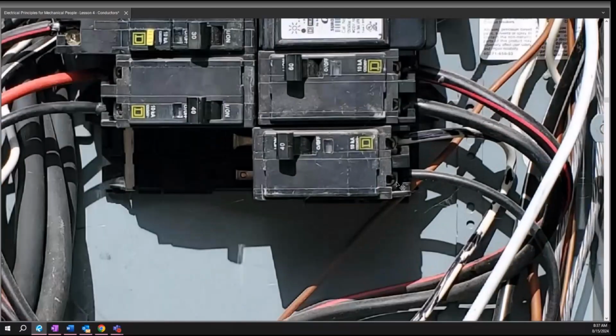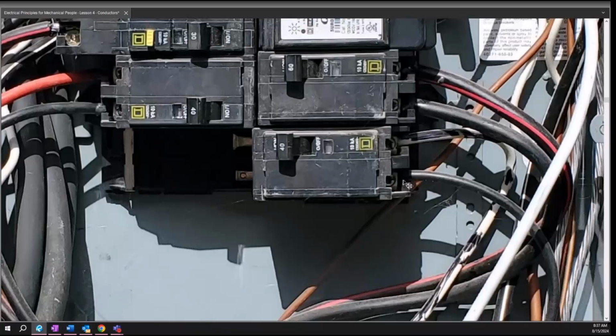The other thing you've got to be concerned about with aluminum, and this is why they don't use it in hospitals very often, specifically can't use it, is that aluminum expands and contracts at a larger rate than copper does. So as you heat up aluminum, it's going to expand more than copper. Now, yes, most, if not all, terminals on breakers and equipment are rated for aluminum and copper. If you're using aluminum, you have to verify it, but regardless, most of them should be rated for both.